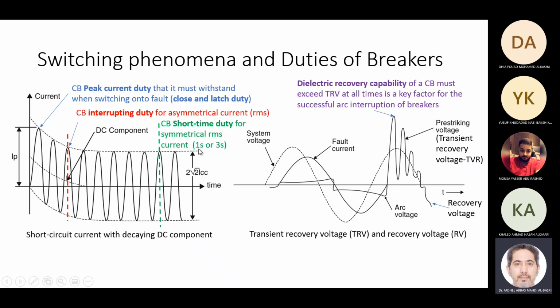They call this specification a short time duty, and it is normally specified for 1 second or 3 seconds or 2 seconds. They are mentioned by the breaker. So this is the maximum time for which the short circuit fault current passes through the breaker while it is closed, and the thermal heat generated by this short circuit can be handled by this breaker without being damaged. Okay, so these are related to short circuit current.